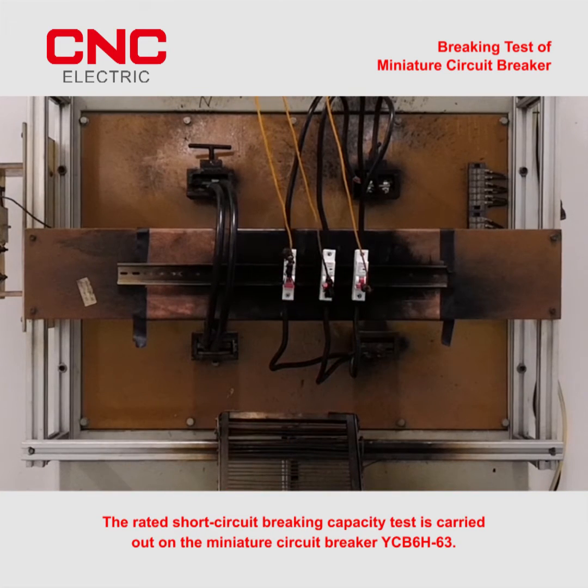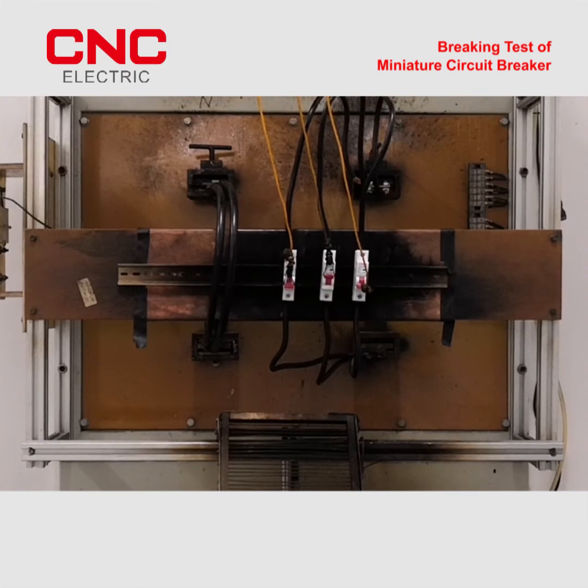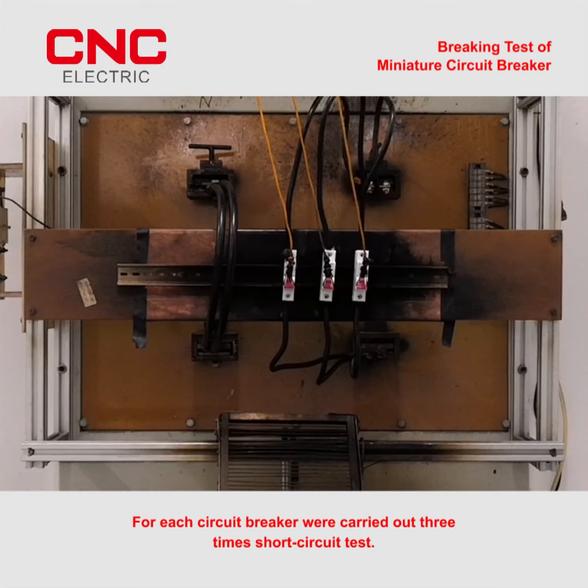The rated short-circuit breaking capacity test is carried out on the miniature circuit breaker YCB6H-63. For each circuit breaker, three short circuit tests were carried out.